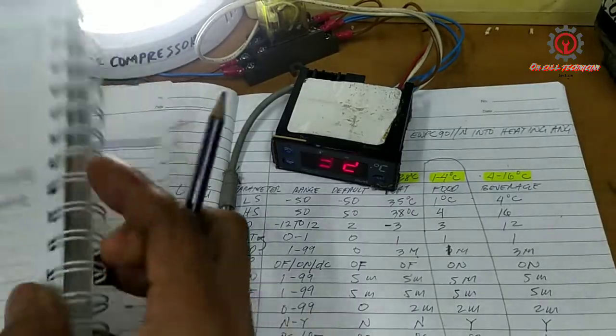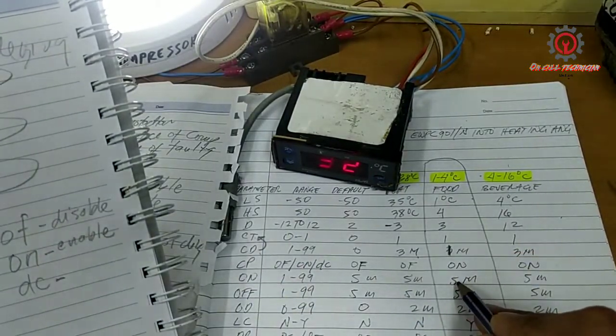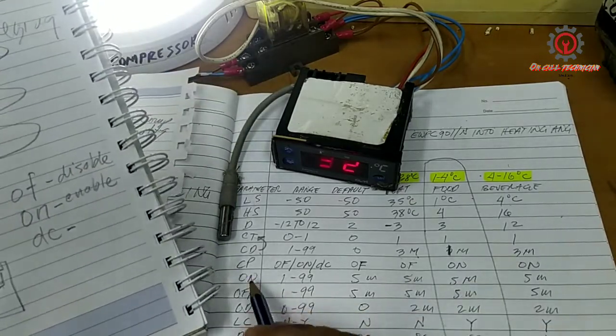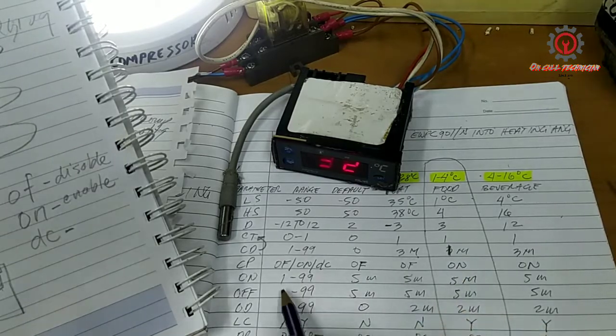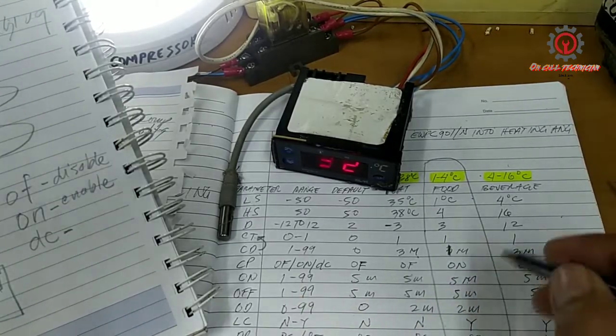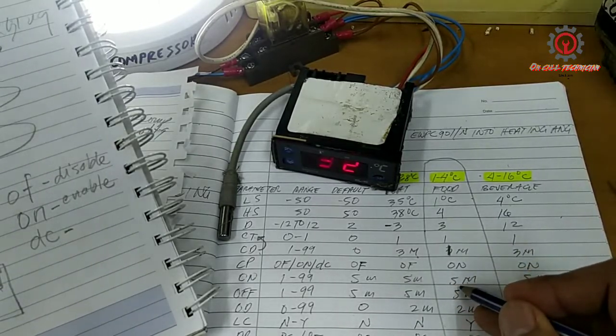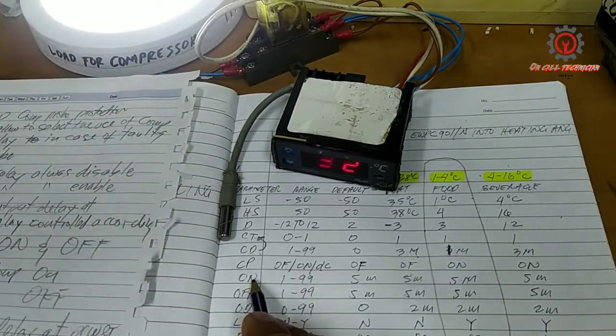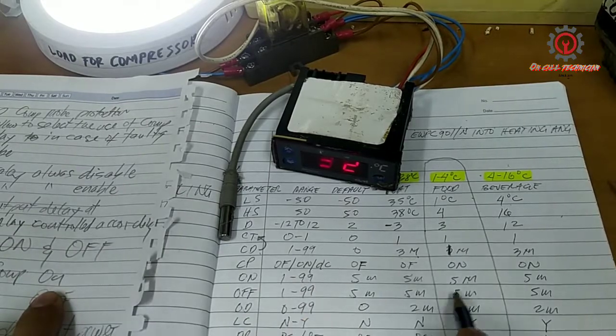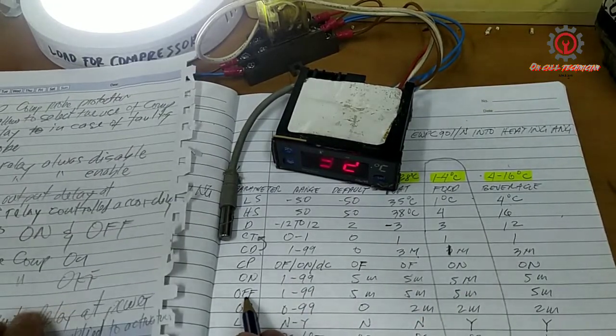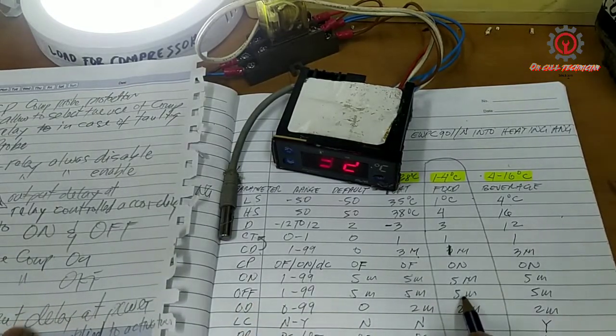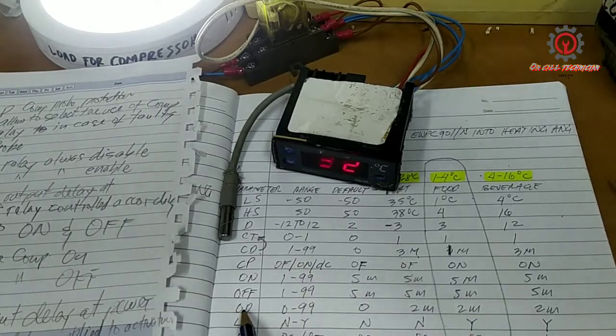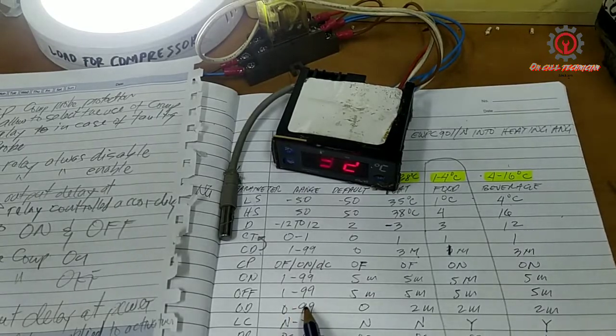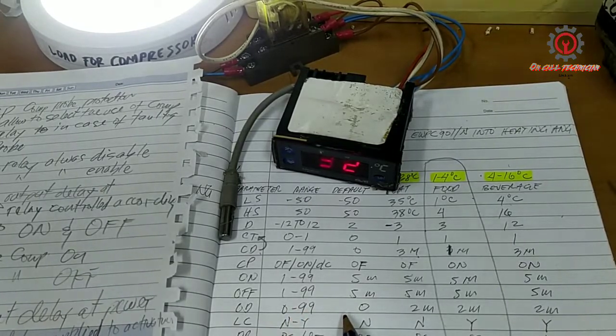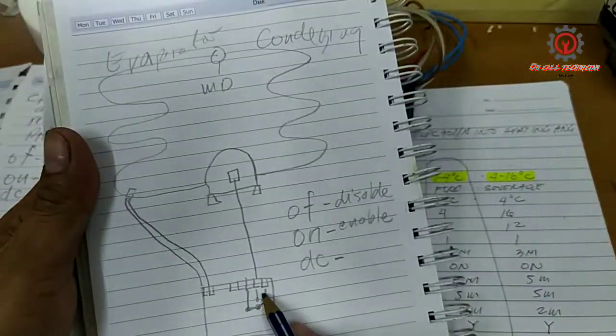So if I'm going to use the DC, I would select this one to be 3 minutes, and the off is 3 minutes. But since I choose the on, I retain the default value. And take note, on, guys, is the time the compressor is on in case of a faulty probe, and compressor time off, and the default is 5 minutes. And the OD, guys, is the output delay at power on, the time delay applied to activation of the relay at startup. And this is our relay delay at startup.